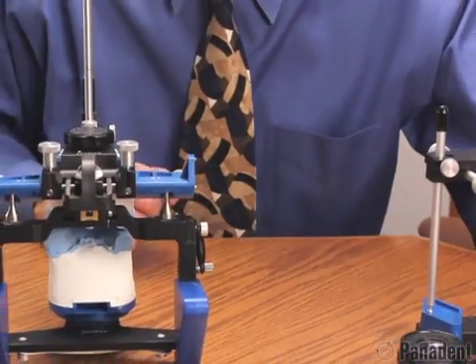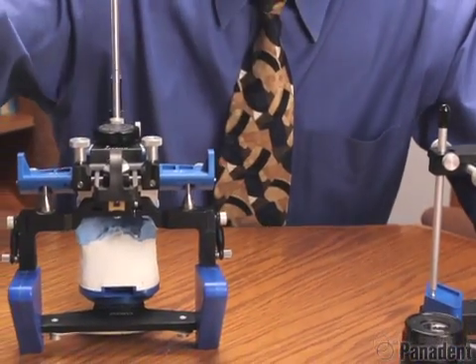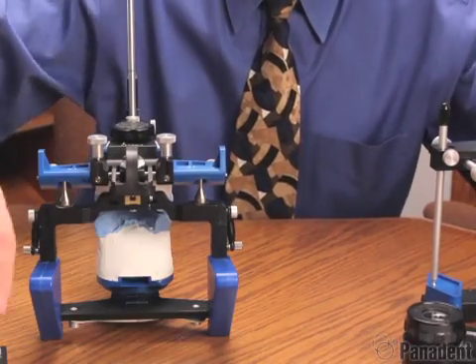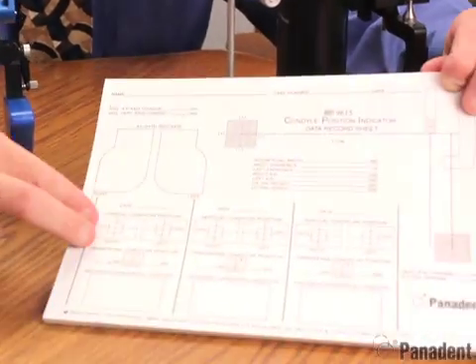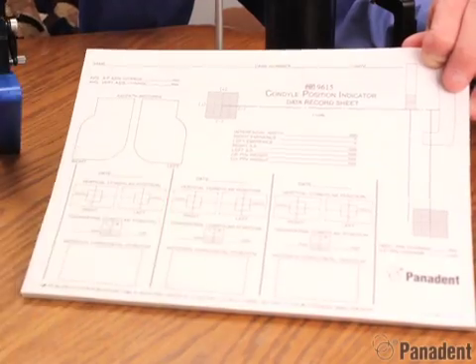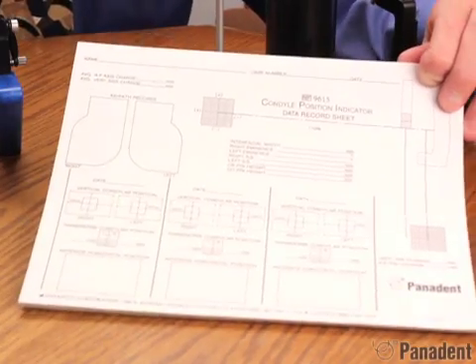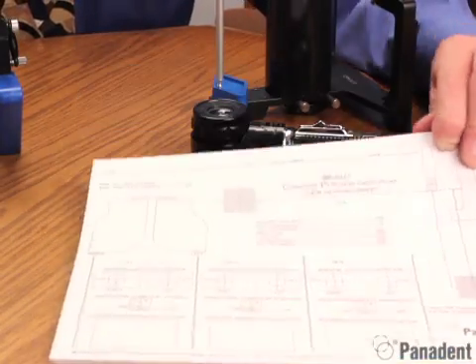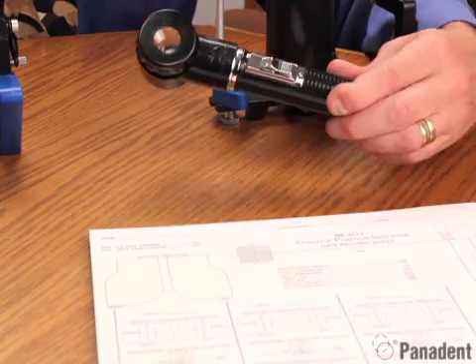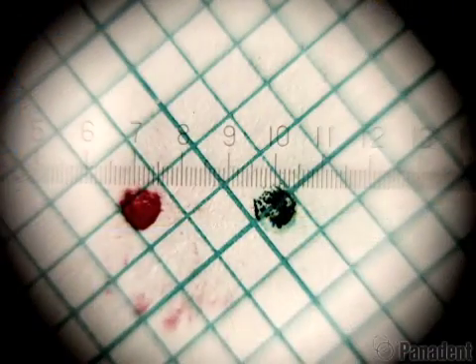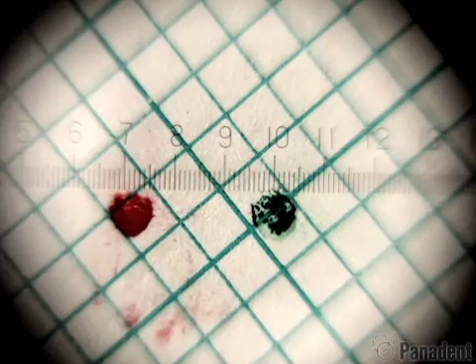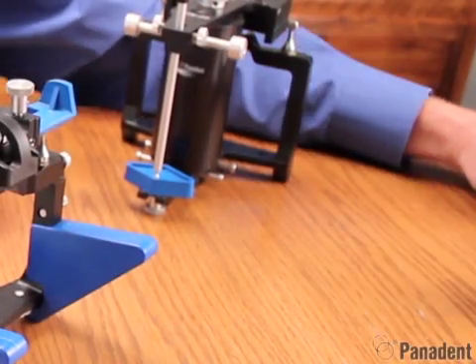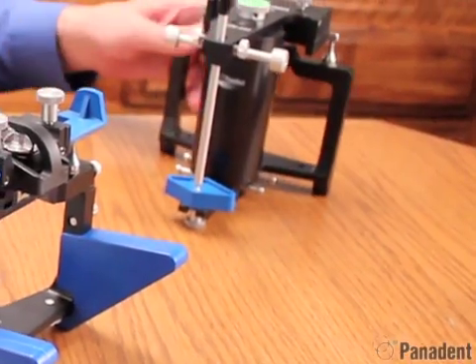With the CPI system, you do get the graph papers included, but you also get a set of data record sheets where you can add different CPI readings or axi-path recordings to the data record sheet. We do have the optional optical resolver, which has a tenth of a millimeter scale built into it so you can read the deviations from CO to CR down to a tenth of a millimeter. Otherwise, the systems are basically the same.